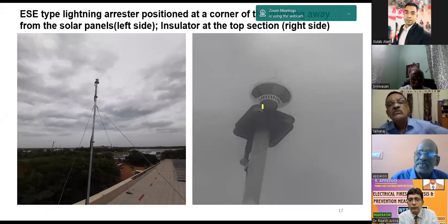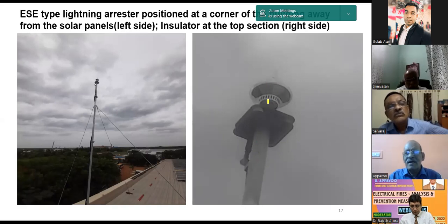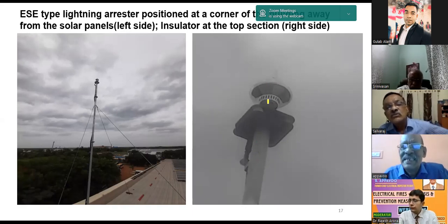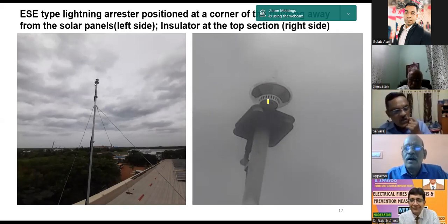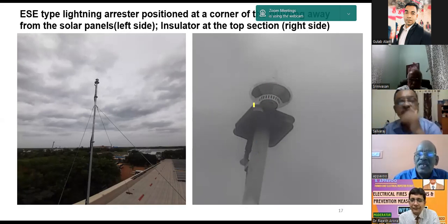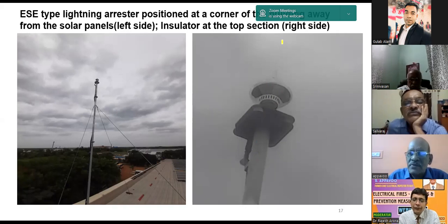And you can see the top section of the ESE. There is an insulator. This is the insulator. You see the insulator. This is a metallic mast, and the top section is some, I don't know what ingredient is available. They claim, several people claim several things. I am not going to debate on that subject much. But I wonder how this small piece of porcelain insulator will prevent the lightning stroke all the way from a few kilometers to the earth. It can be prevented and diverted through the cable.